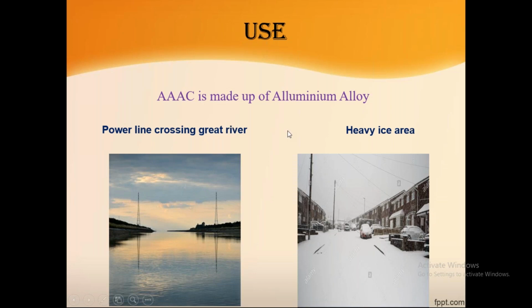Next is AAAC - all aluminum alloy conductor. This is made up of aluminum alloy and has more tensile strength compared to AAC. This type of conductor is generally used in power lines crossing great rivers. Why? Because if floods occur, there's a chance of soil corrosion, so the tower must withstand this with a conductor that is less weight - aluminum is lighter compared to steel and copper. That's why this conductor is used in river crossing areas.